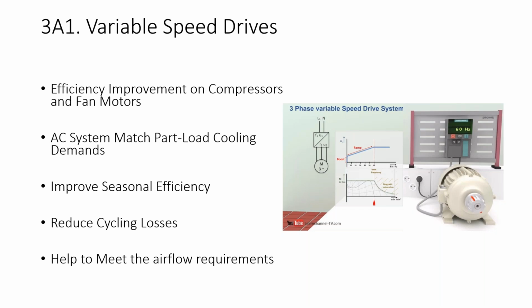Variable speed drives. Variable speed drives improve our compressors' and fan motors' efficiency big time. It works in a way that if we have a high load, the fan speed will go high. If we have a moderate load, the fan speed will go down. And if you have a very minimum load, the fan speed will go low. As the fan speed goes low, we will save our electricity. It's not like a one-speed motor, which either goes on or off. It is a variable speed which we can adjust and which can be controlled automatically as per our load requirements. So it improves our efficiency big time in centralized air conditioning systems.